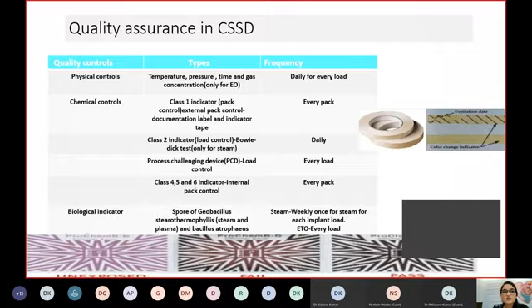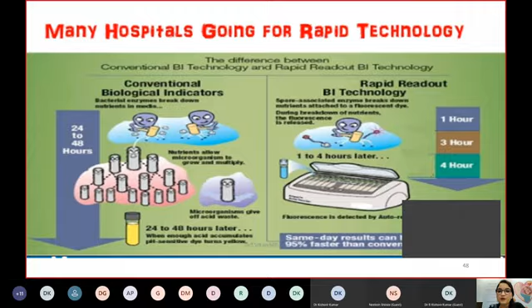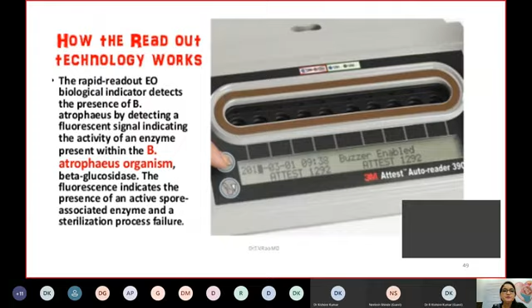They test the activity of the bacteria, and if this is successful, then your CSSD recall problem can be addressed to a very large extent, because then you can wait for the biological indicator result to come out, and only then dispense your other sterile equipment to the other departments. So this is what I was talking about. They test the activity of the bacillus.